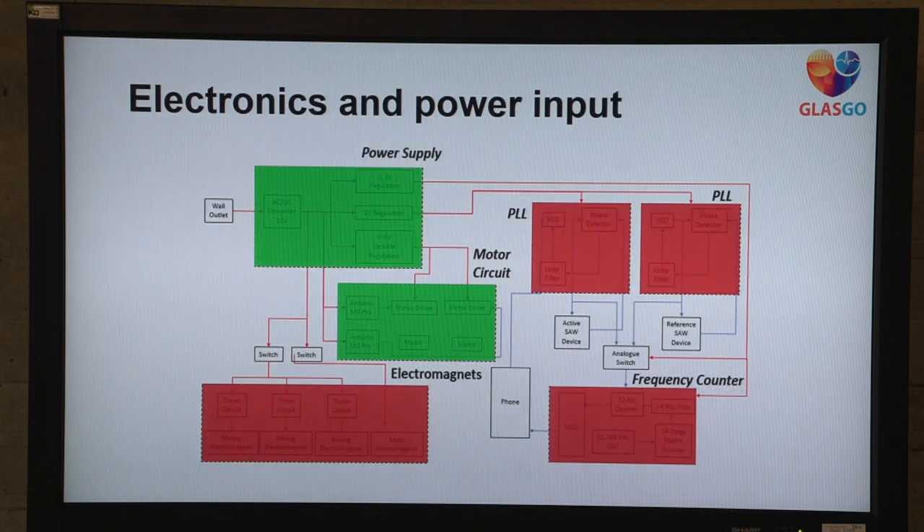Regarding the electronics and power input: in the initial plan, we had a phase-locked loop circuit which would have identified the frequency, and then a frequency counter would have translated our phase frequency into a concentration of NT-proBNP. The electromagnets would have aided in mixing the beads and the magnetic particles, and the motor circuit and power supply would have pumped the fluids through at set time intervals.